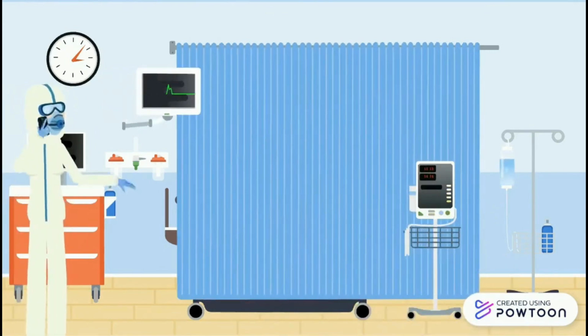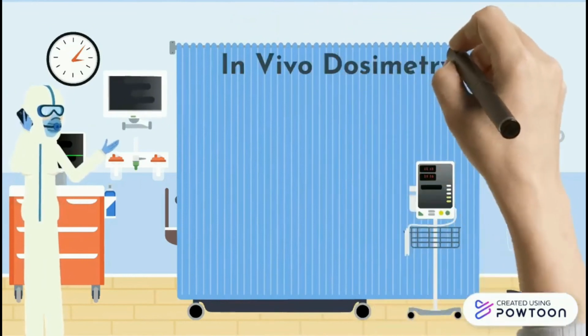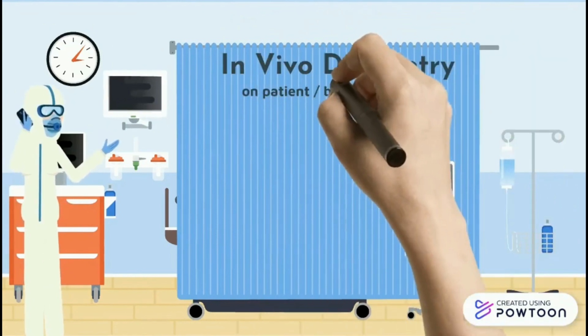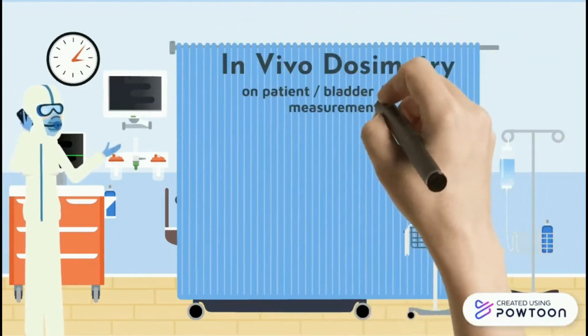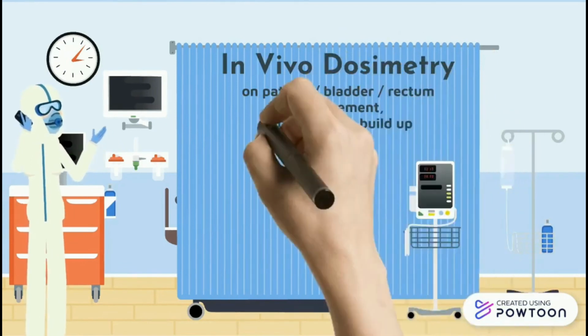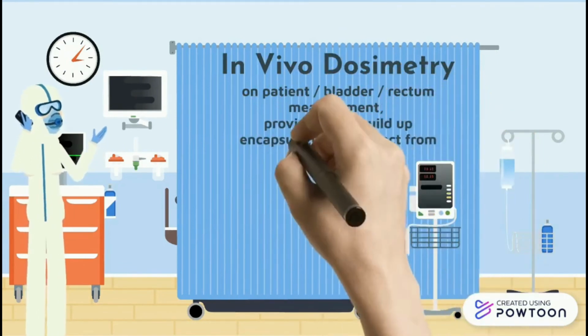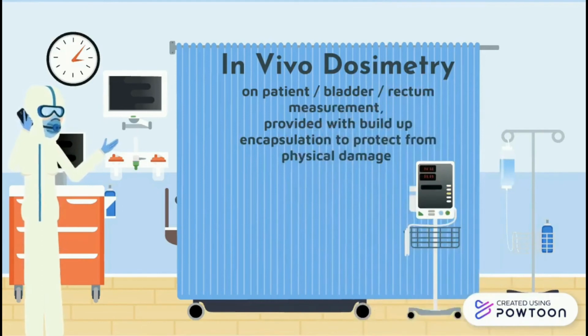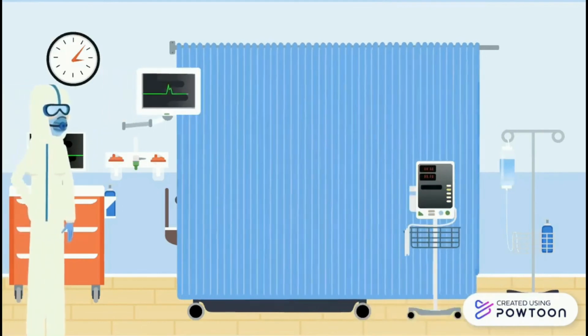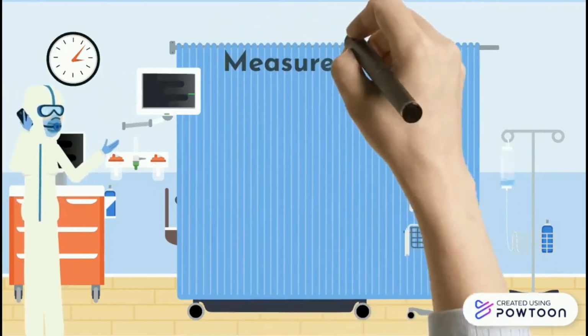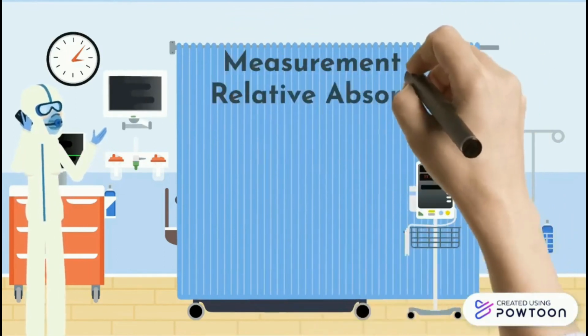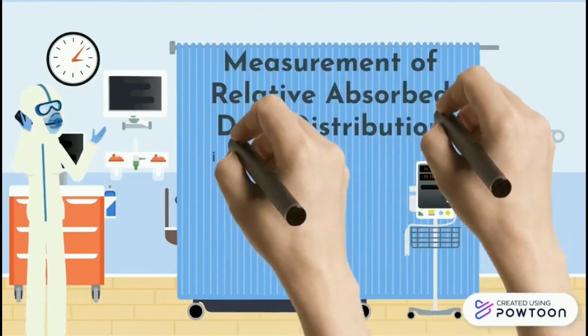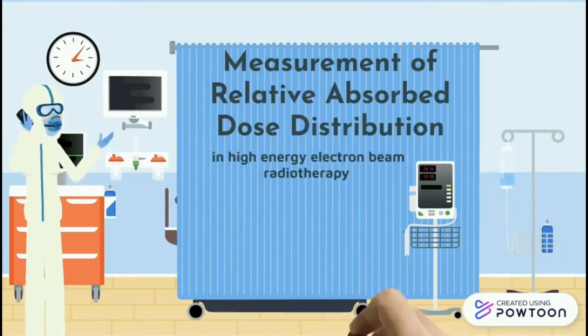Silicon diode dosimeter is also used for in vivo dosimetry, which is used on patients, for bladder or even rectal measurement, provided with build-up encapsulation to protect from physical damage. Silicon diode dosimeter can also be used for measurement of relative absorbed dose distribution in high-energy electron beam radiotherapy.